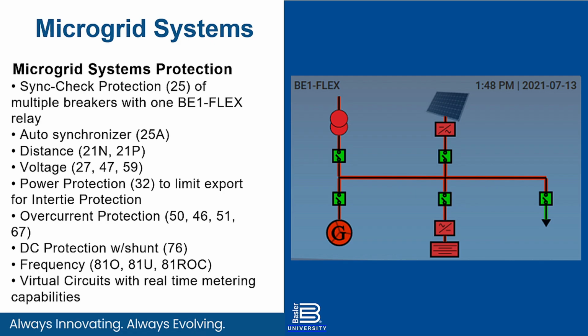One of the more specific ones that's common in a lot of generic microgrids is what you see in the top middle. It's a solar panel, and those are DC power. So you've got the inverter coming in. The Flex has the ability to bring in shunt inputs instead of current transformers, and with that we can actually see direct current overcurrent. Something that's not very common in many protective relays, and we can do it in addition to all the other things that we're doing.